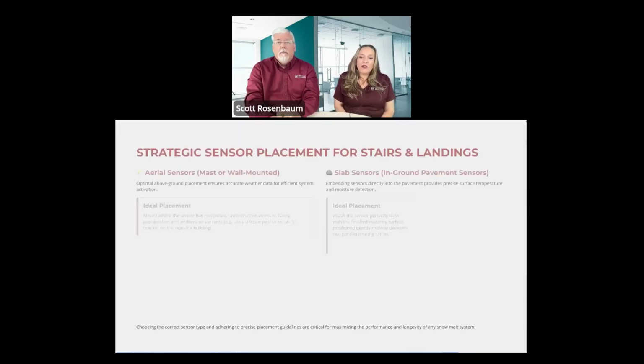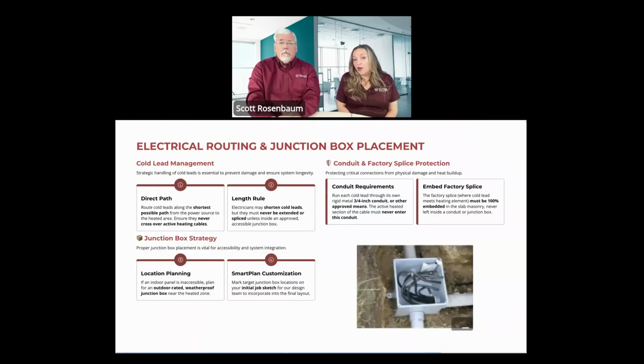Right. So placement of those, again, you've got to let us know ahead of time where you're going to put those on your plan. I had an example for a guy just yesterday, he wanted a 3x60. We don't actually have a 3x60, right? So I advised him that we could do a 3x30 and another 3x30, and then you butt the two starts together and you put one J box coming out to the side. Unfortunately, he didn't want to do that. He wanted it to be continuous. He's like, no, I don't have anywhere to put a junction box. But we did have to talk him around to figure out a way to do that. So, yeah, you definitely have to think about the J box placement ahead of time.